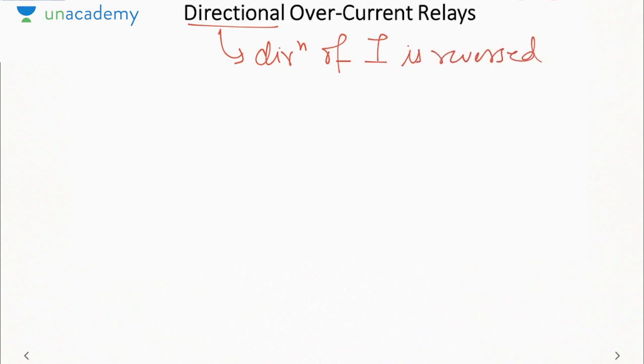The next type of relay is called the directional over current relay. Now as I told you, in directional relays, what is the basic assumption? That the current direction gets reversed. So the directional relay is based on the assumption that the direction of current is reversed. But in addition to that, what we are checking is that the current magnitude should be high to indicate that there is a fault in the system.